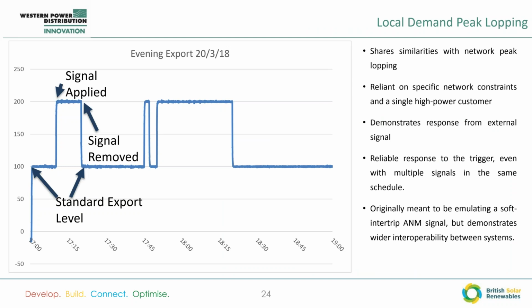We've then got the local demand peak lopping. This is the only system that responded to an external signal rather than just relying on pre-timed schedules. So here you can see that we've got a standard export level, the 100 kilowatts, as if we're supporting the network between 5 and 7. And then if the battery receives an external signal, like an active network management signal, a soft intertrip, the battery increases its export, and then once the signal is removed, it decreases.